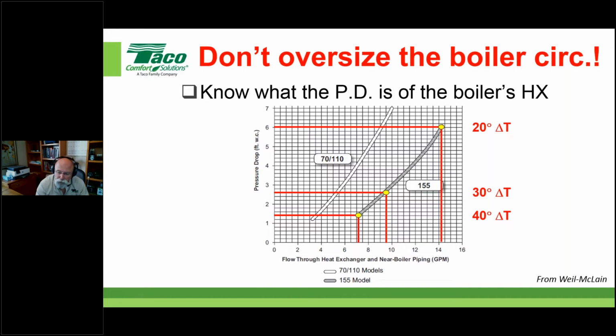Here's one thing I do want to point out. Some boiler manufacturers, including this one, will actually throw a little fudge factor in there. It's not really a fudge factor. They're actually anticipating a certain amount of piping, valves, fittings, apparatus, incidentals on that piping that gives you a total pressure drop through the heat exchanger. Now, you just don't put the belt and suspenders on here, right? If you know they make this note here and they're mentioning near boiler piping, then don't add additional pressure drop for that. It leads to circulator oversizing, just like we always talked about.